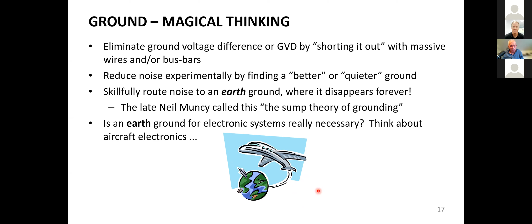Absolutely not true. If you think about the towers that carry utility electricity around, all of those are grounded, and in a lot of places the neutral is tied to an earth ground stake. If you look around your neighborhood with above ground utility wiring, about every third or fourth pole you'll see a ground wire running down the side of that wooden pole. That gives lightning a convenient place to go.